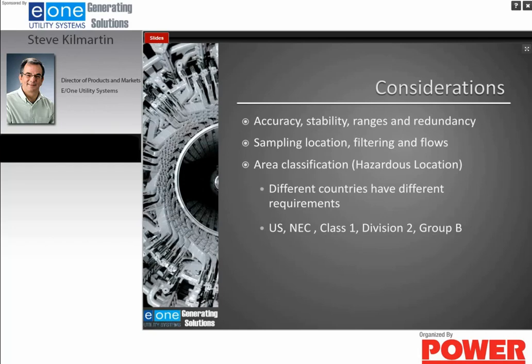I would also recommend, as far as ranges, that it is a triple range analyzer, and that you want it to measure hydrogen and air, hydrogen and CO2, and air and CO2, so that you can use it not only during normal operation, but also during the purging of the generator. Some manufacturers and some utilities like to have redundant analyzers.